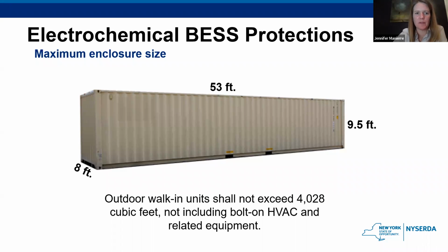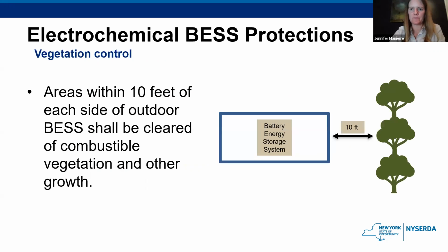All right. Yeah, I'll try to get through the remainder here. I know it can be a little dry just going through code requirements, but it's important to know what's in there and we want to make sure we can get those credits out the door by covering all of the material. I'm going to try to breeze through. So, the vegetation control requirement: any areas within 10 feet of the system need to be cleared of combustible vegetation or other types of growth. This is another instance where large-scale fire testing can allow the code official to approve a reduced clearance beyond 10 feet, but otherwise 10 feet of clearance.